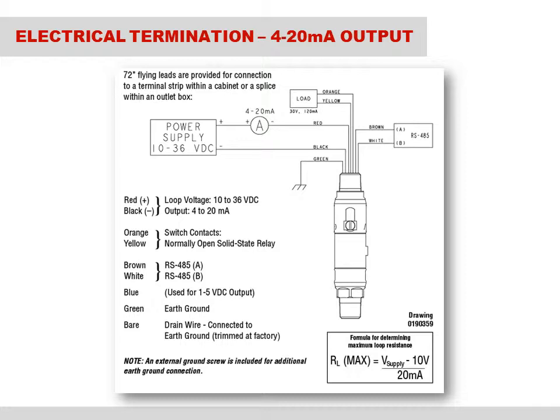For example, if one does not need the configurable solid-state switch output functionality of the 815 PT, one would simply not terminate the yellow and orange conductors. The same can be said for the brown and white wires. If one does not require Modbus RTU serial communications on an RS485 twisted shielded pair network, then it isn't necessary to terminate the brown and white wires.